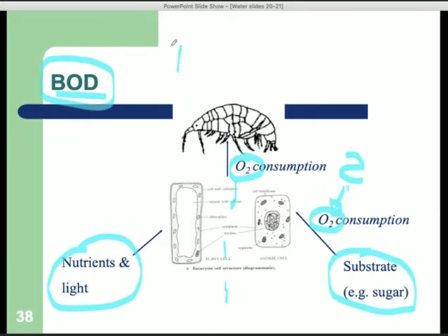In that case, that would be the standard BOD. This is turning terrible though. This isn't meant to be BOD, and that's meant to be 5. So you're getting the BOD5. So 5, the index 5 here means 5 days. And that is the standard measure that you use in industry. You measure the oxygen reduction due to waste in the water after 5 days.